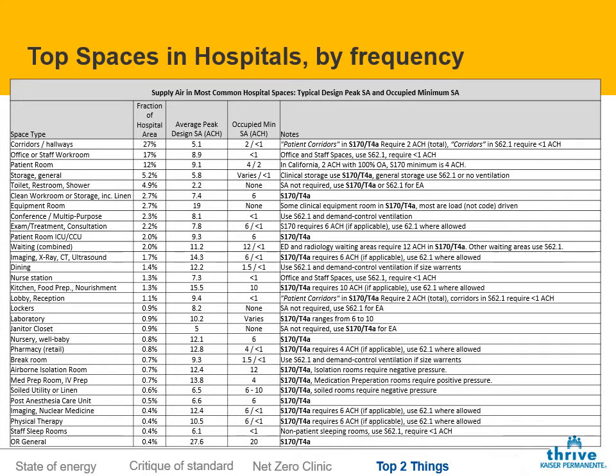The second most common space in hospitals is administrative areas. It is almost 20% of the building footprints. And our design engineers have been putting in 8 or 9 air changes of supply air on average. Dude, you can turn that down 90%. Worst case code minimum overnight is California. You could drop down to 25% of 4 air changes, which is 1 air change. The overnight minimum is very, very low in those spaces.